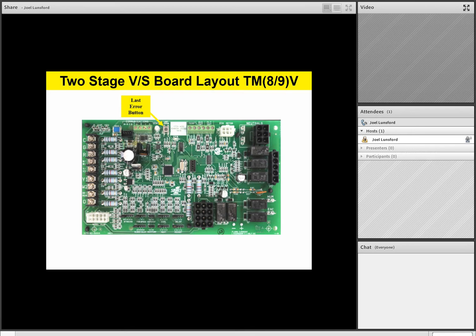If you look closely on the board, just a little bit below and to the right of the last error button, there's a CFM light. This is a unique feature of our variable speed control board in the fact that it will flash 1 time for every 100 CFM that the fan is blowing. So this is a nice little visual check on our variable speed products, because once we set up our airflow, it's nice to visually check how fast that fan's blowing and what it's doing as far as CFM. It will flash 1 time for every 100 CFM that it's delivering. It'll then pause about 2 seconds and then repeat the flash code, and it will do that indefinitely as long as the fan is running.